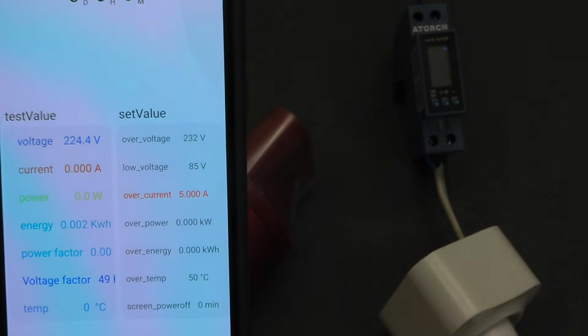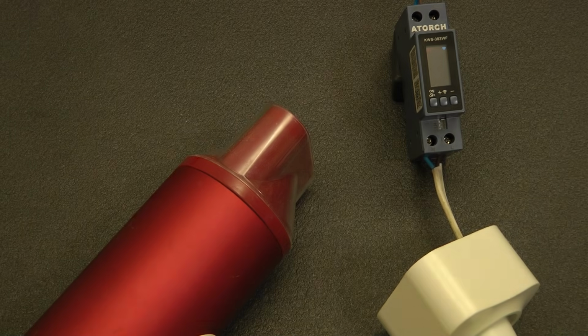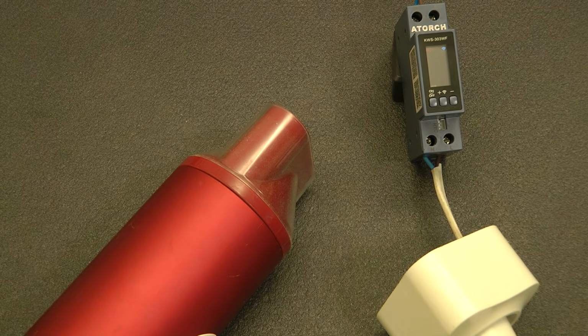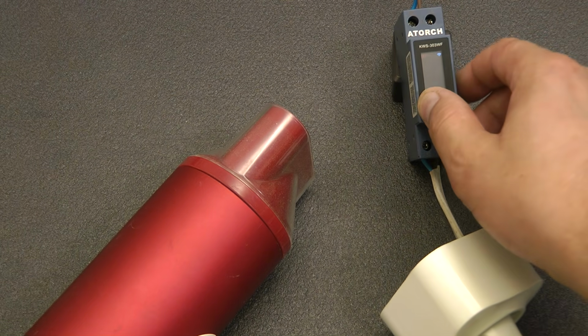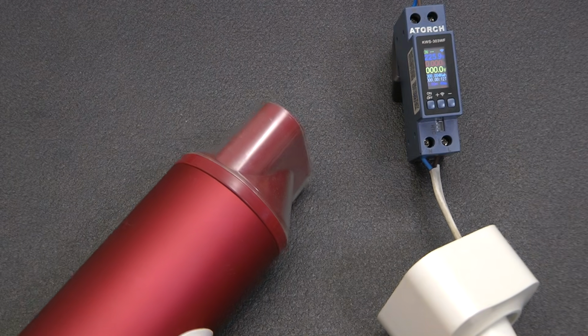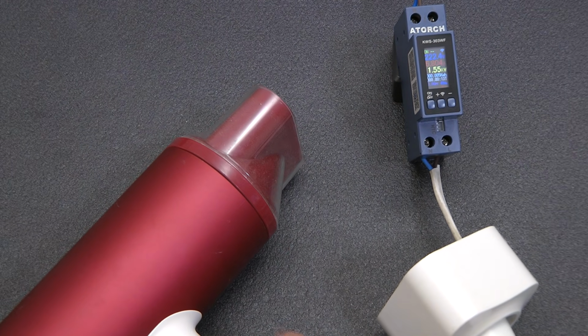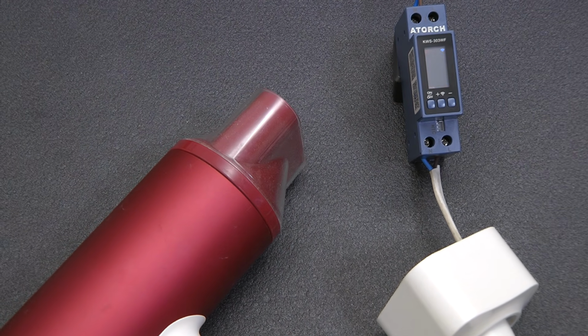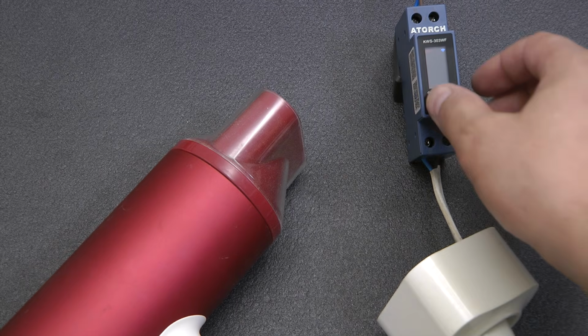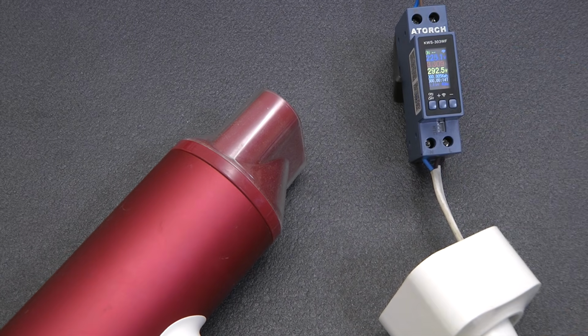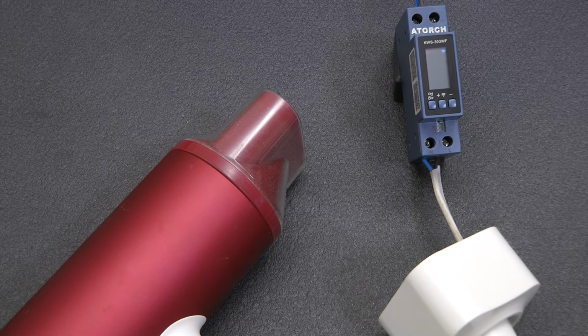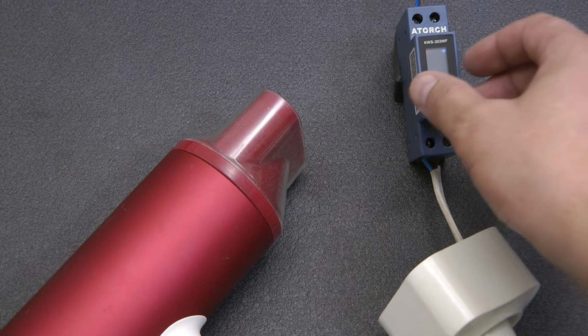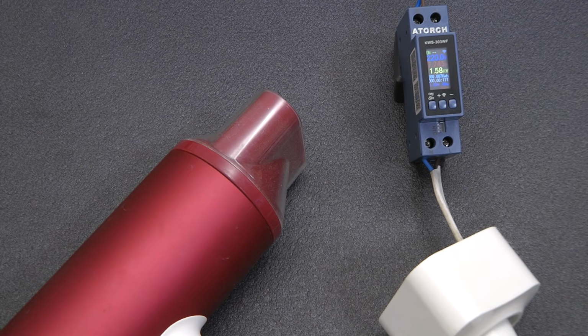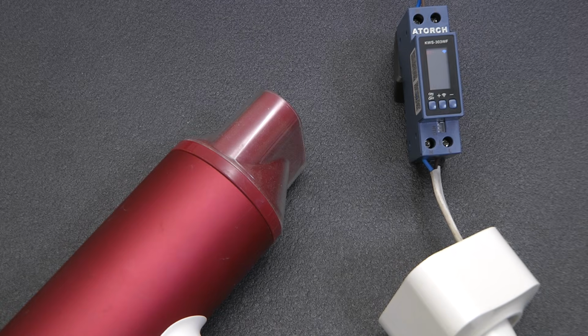Now let's check shutdown by maximum current. I set the limit to 5 amps and connect a regular hair dryer as the load. I turn it on, and after about 2 seconds the relay disconnects the load. We repeat it once again. I turn it on manually, and it disconnects again. So the claimed protections really do work.